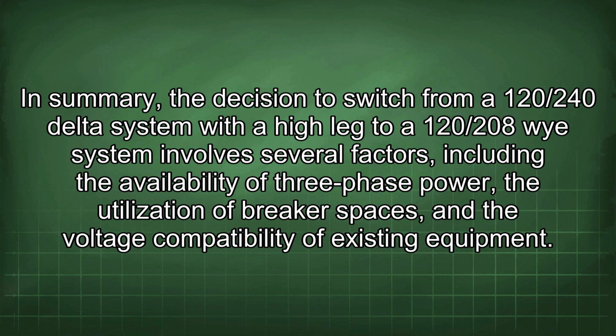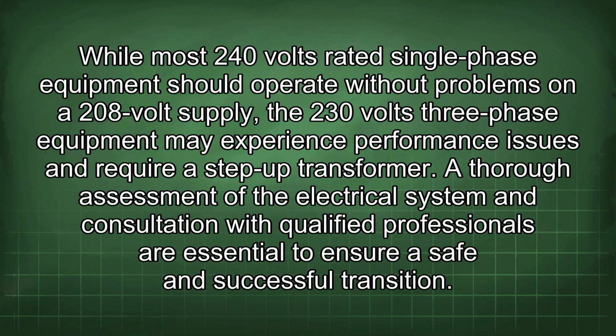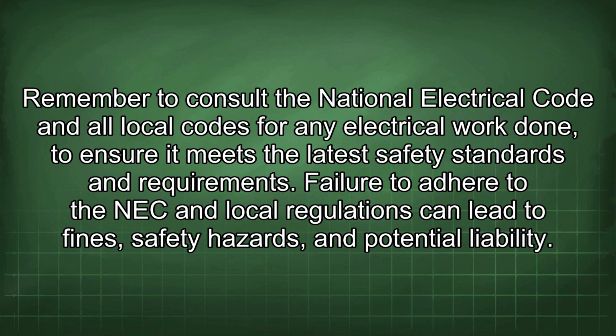In summary, the decision to switch from a 120/240 delta system with a high leg to a 120/208Y system involves several factors, including the availability of three-phase power, the utilization of breaker spaces, and the voltage compatibility of existing equipment. While most 240 volts rated single-phase equipment should operate without problems on a 208 volt supply, the 230 volts three-phase equipment may experience performance issues and require a step-up transformer. A thorough assessment of the electrical system and consultation with qualified professionals are essential to ensure a safe and successful transition. Remember to consult the National Electrical Code and all local codes for any electrical work done to ensure it meets the latest safety standards and requirements.